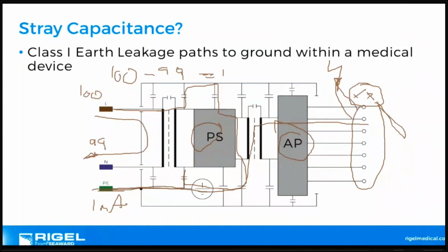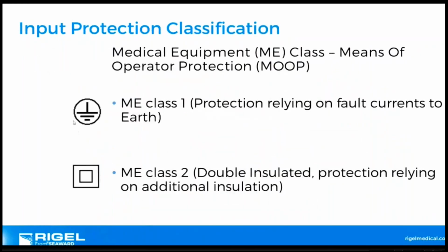Let's get rid of those drawings. So in the way that we categorize input protection and output protection and safety, you've got means of operator protection, so the person operating the medical equipment, and then we have the patient, so that would be the means of patient protection. The means of operator protection is to make sure that the operator is free of macro shock and micro shock. Protection is generally, on class 1 equipment, the main protective earth. So you've got to protect the earth from any exposed, touchable metalwork that's conductive, and any fault current should flow through that earth.